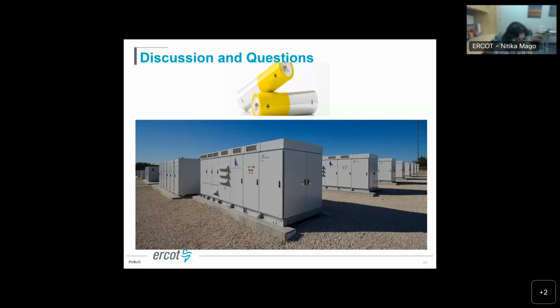They are also able to qualify for and provide an ERCOT-specific fast frequency response service, if they choose to operate in that mode. The trigger setting for that capability is 59.85 hertz, and the response time is 250 milliseconds.